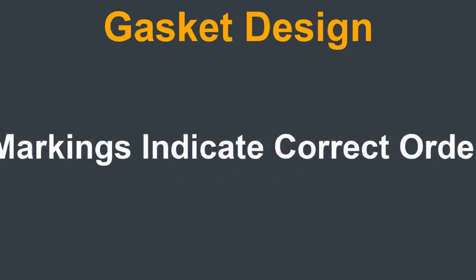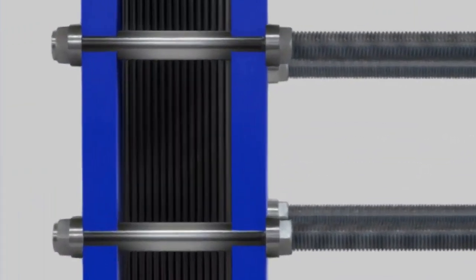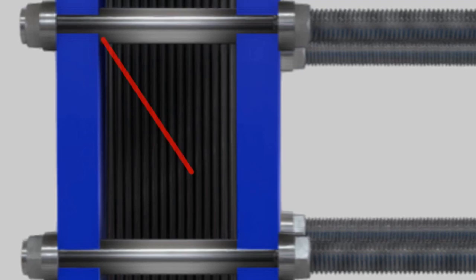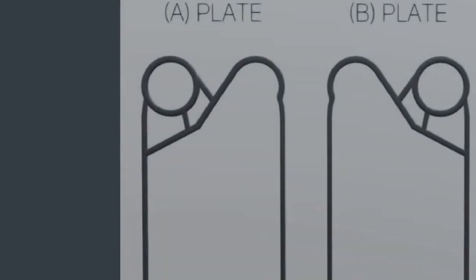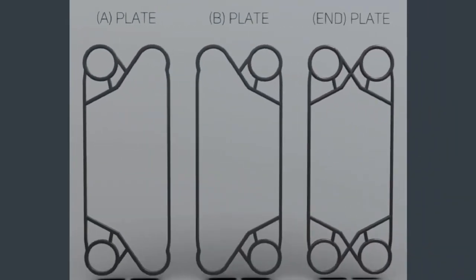Another way to check the order of the plates is to spray paint a diagonal line from the top left to bottom right of the entire plate stack. Although we have only shown 2 gasket designs so far in this video, there are actually 3. Gaskets alternate throughout the heat exchanger except for the first and last plates within the plate stack, which press against the fixed and movable covers.